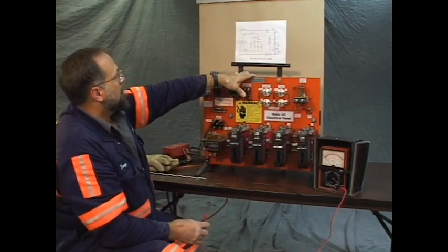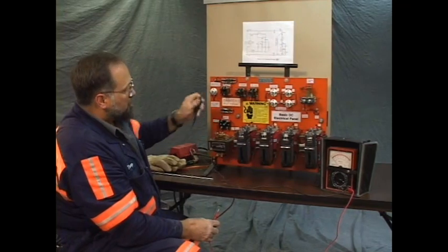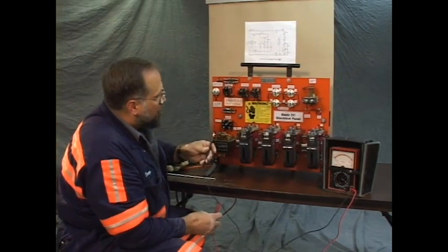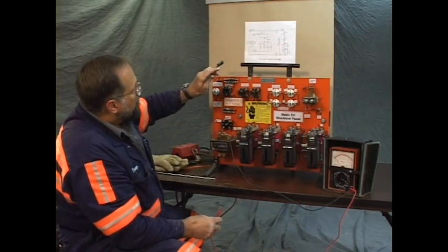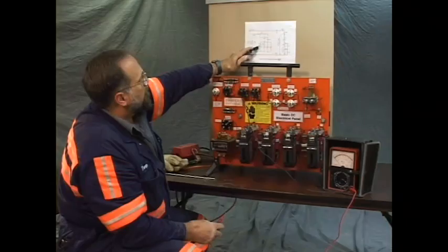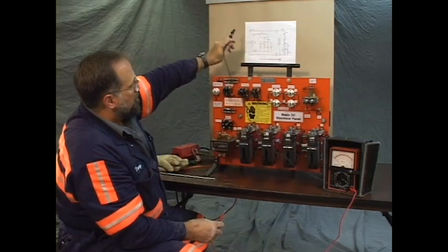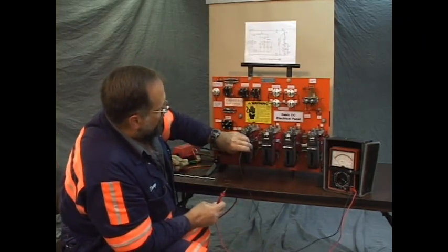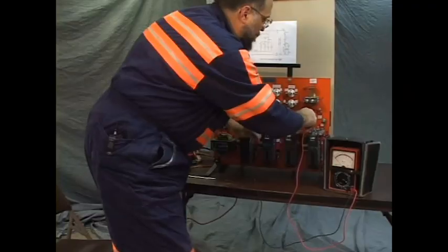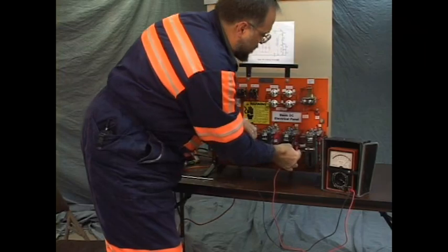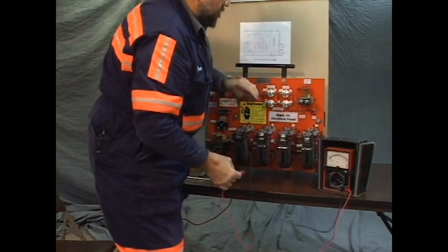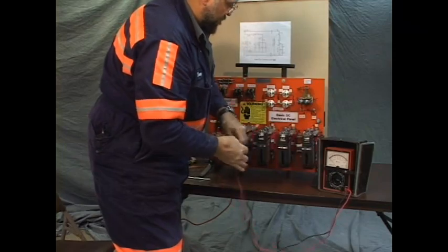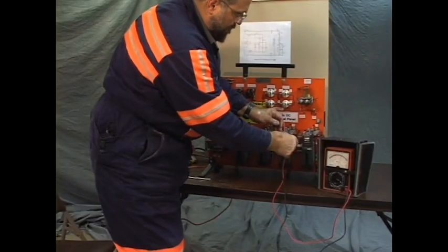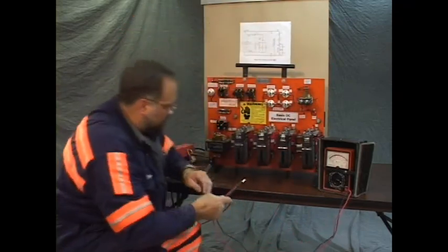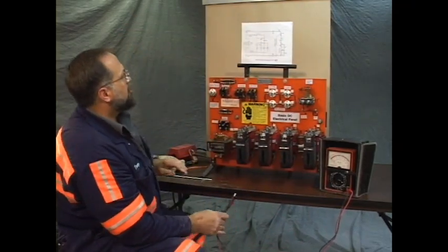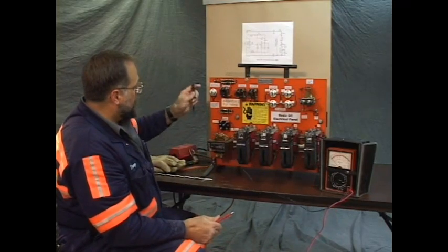Okay. With the note that this is the first time I have to move my negative meter lead probe, I'm going to check now this short wire here from the load side of the 1A mercury tube to 2A. Positive of 2A coil, and it's good. From the load side of the M2 mercury tube to 1A coil, and it's good. And we've completely checked the positive side of the control circuit. Finding no error, let's proceed to the negative side.